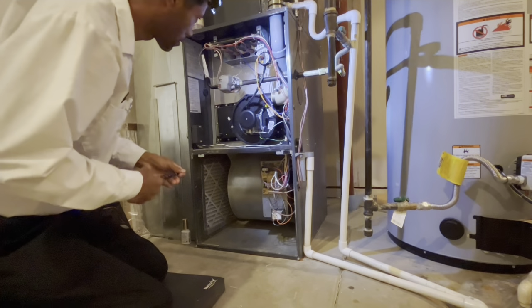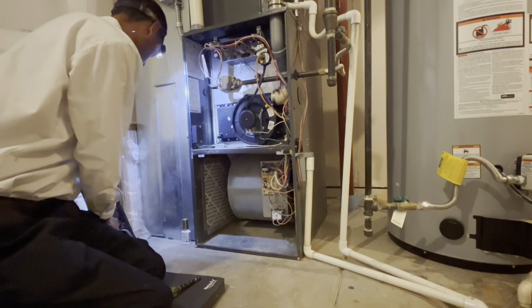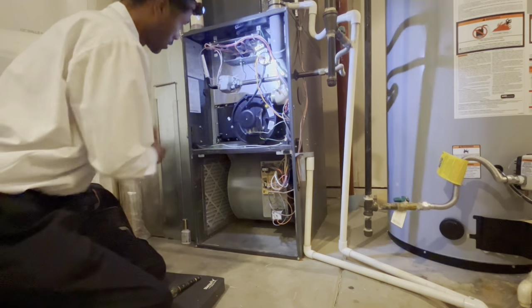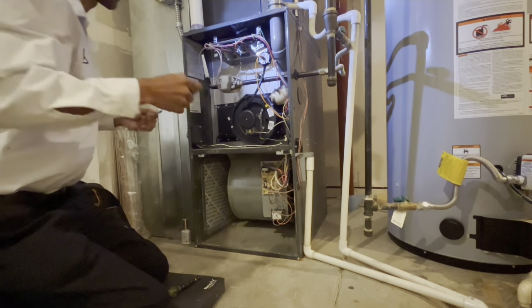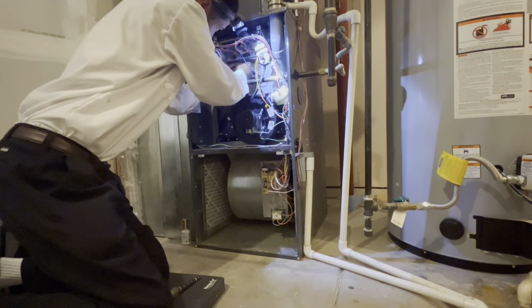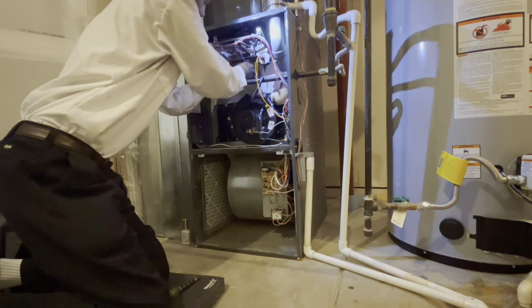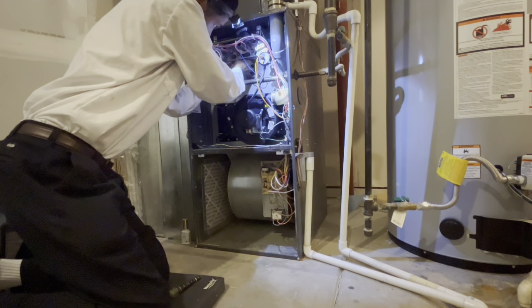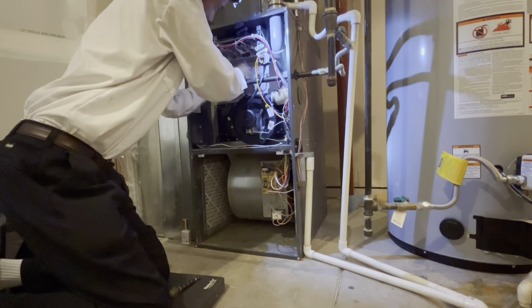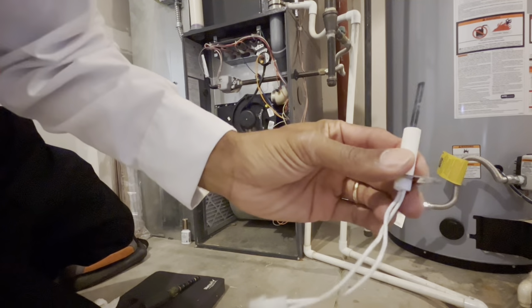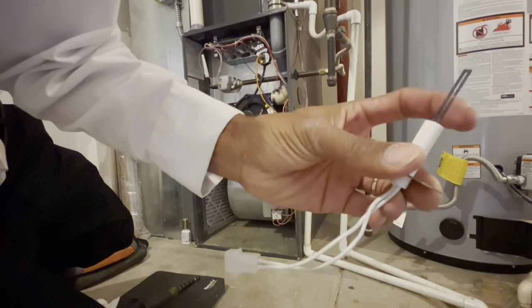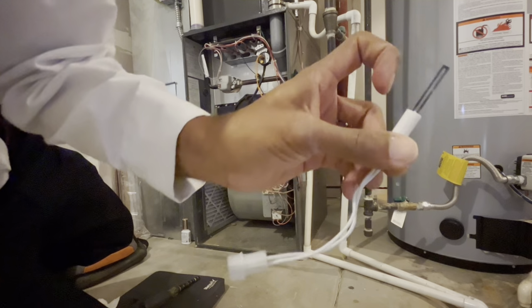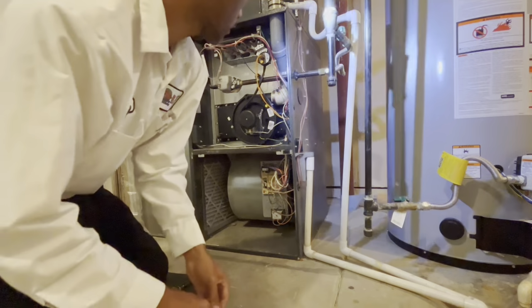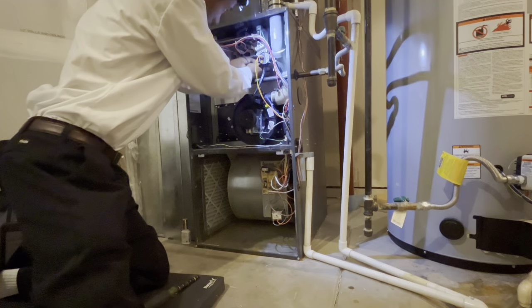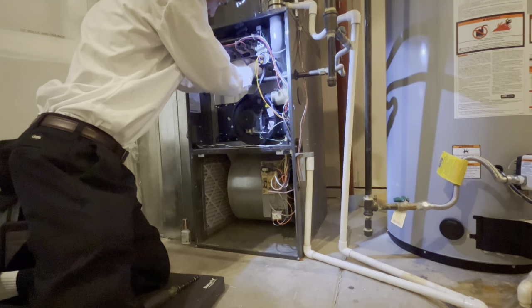So I normally start with the flame sensor and the igniter, those two components on the furnace. They're usually held in with, I think it's a 1/4 inch nut or screw, I guess you want to call it. So I have a little short stubby Klein socket screwdriver. That's the igniter right there. You see on the right side of the middle, there's a little whiteness there, and that's where it will eventually burn out and it will not complete the circuit. So that igniter doesn't look terrible, but it is showing some wear. I'd probably say it's about 50% used up.